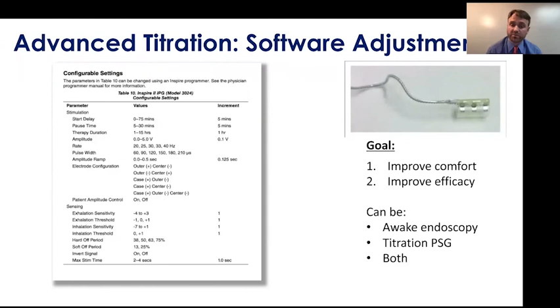So all of the advanced titration that we're talking about is a software adjustment. They don't need more surgery for that. These parameters that are listed over here can all be adjusted just with the programmer. And in particular, the electrode configuration, as you can see on the picture to the right, the cuff of the electrode actually has 3 small electrodes, and the polarity can be switched around, turned off, things like that, to get 5 different configurations. The general setting, or the default setting, I should say, is usually adequate for 80-90% of patients. But if it's not, we have quite a bit of variability to change things to improve the efficacy and comfort of the therapy without any sort of invasive procedure for the patient.